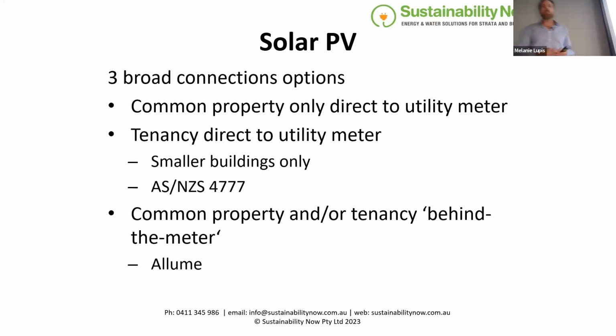One other problem you can face if you're sending electricity from the solar system to the tenancies is that Australian Standard 4777 says once you get over 30 kVA, or 30 kilowatts, of inverter size at one connection point to the grid, you need grid protection relays — additional protection. If you have multiple systems installed at that connection point, you need multiple relays: a master relay and sub relays, which can get very expensive. So that can be a problem connecting to tenancies if multiple systems add up to more than 30 kilowatts.